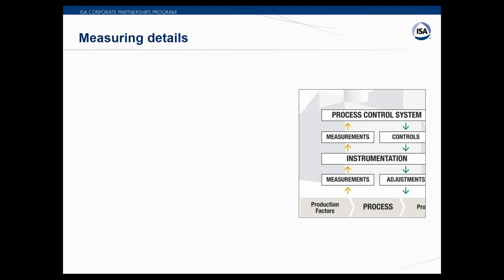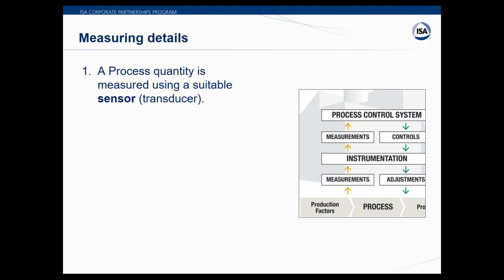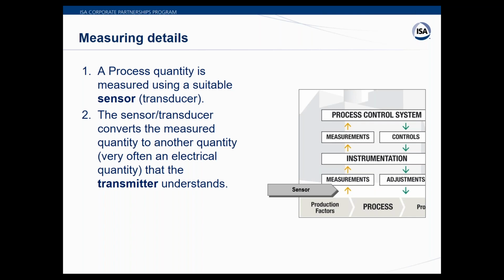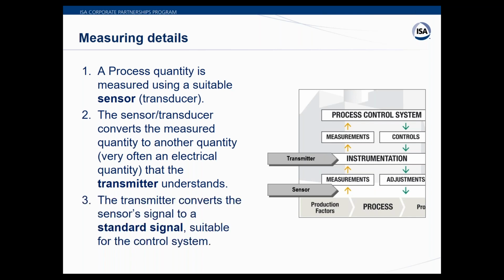When we talk about the little chart I had, obviously the first component is a sensor or a transducer. So that's down at the very beginning of the measurement. Typically, sensors are then connected to transmitters or they're built into transmitters so that we can send the measurement into our control system. And then finally, something has to receive that signal, whether it's a PLC or the DCS. So that's the process flow of making a measurement. You can see it can be complex with multiple devices in a loop. It's important that you understand how accurate the sensor is, how that impacts the accuracy of the transmitter, and then how that impacts the interpretation by the control system so that you get good control elements coming back out of the system.